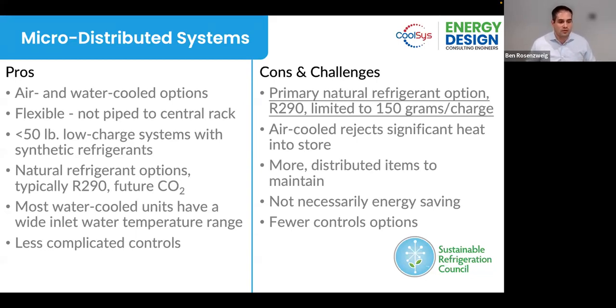Most water cooled units for R290 and other systems have a very wide inlet water temperature range, so you don't need a chiller in order to run those. And there's much less complicated control systems. Many of these pieces of equipment and cases are controlled similarly to a refrigerator at your house, where you plug it in and select the temperature and let it do its thing. Some of the challenges are, and really the primary challenge is, that right now, the most popular and widely available refrigerant for self-contained micro-distributed systems with a low GWP is propane.